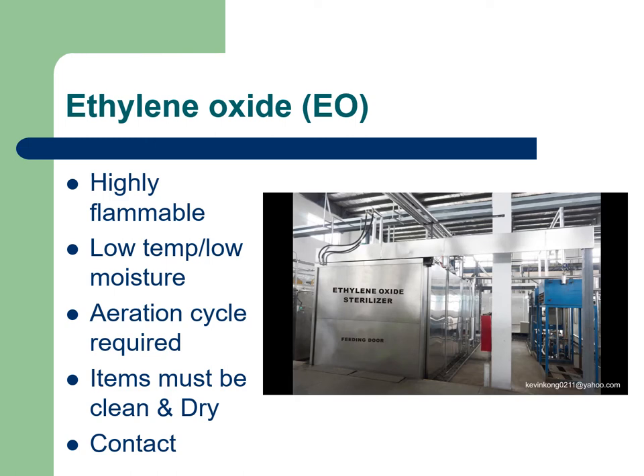Facilities that have these EO sterilizers have to have special alarms. At the VA, they called them the sniffers, and the sniffers can detect dangerous levels of ethylene oxide, and they would alarm if they did detect that.